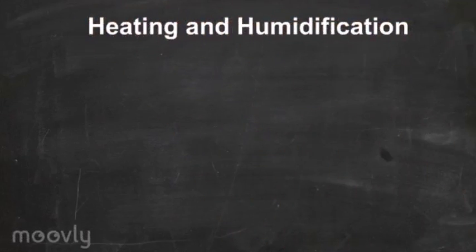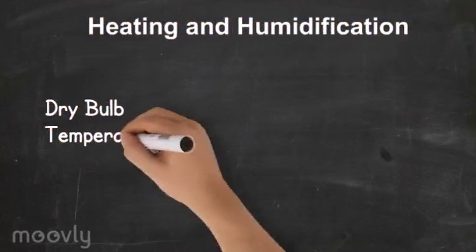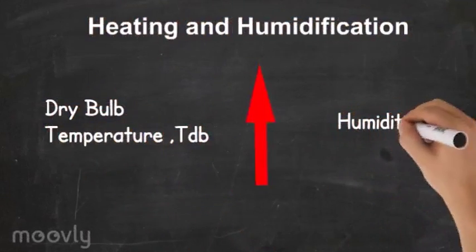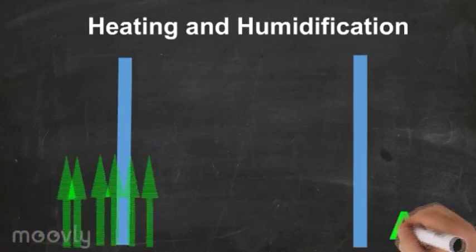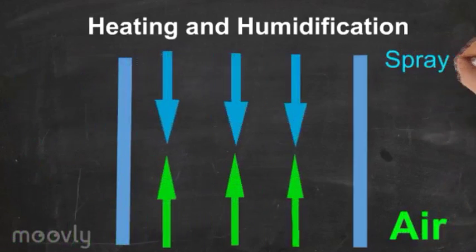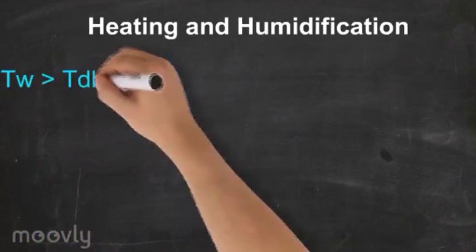In heating and humidification psychrometric process of the air, the dry bulb temperature as well as the humidity of the air increases. The heating and humidification process is carried out by passing the air over spray of water which is maintained at a temperature higher than the dry bulb temperature of the air, or by mixing air with steam.